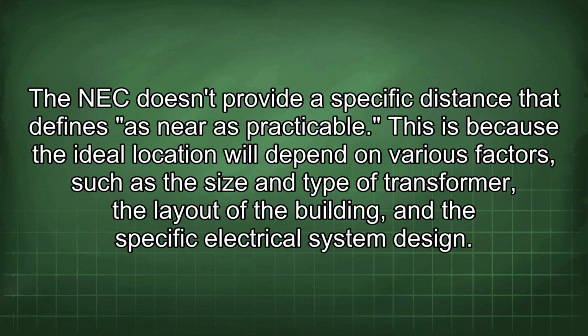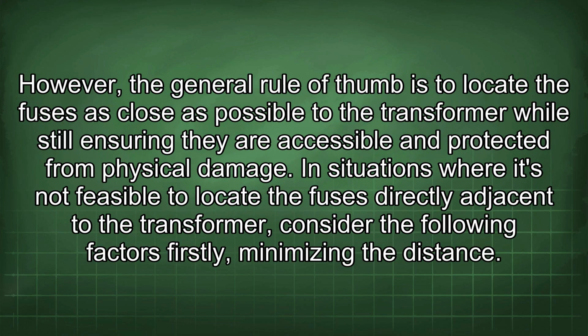The NEC doesn't provide a specific distance that defines as near as practicable. This is because the ideal location will depend on various factors, such as the size and type of transformer, the layout of the building, and the specific electrical system design. However, the general rule of thumb is to locate the fuses as close as possible to the transformer while still ensuring they are accessible and protected from physical damage.